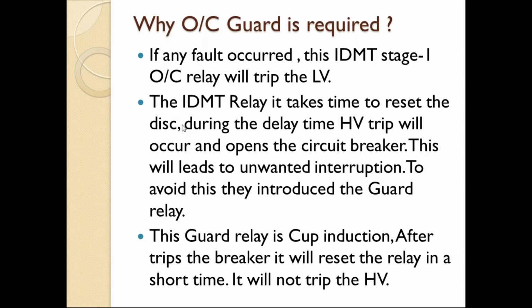Due to some delay in time, there may be an HV breaker trip also. That's the reason we are using this O/C guard. Mainly this IDMT has some time lagging — it's an old type of relay, so we use this guard type relay to overcome and avoid that mal-operation. This guard relay is cup based, so the time taken to reset the breaker is very short. That's why the HV trip will not happen.